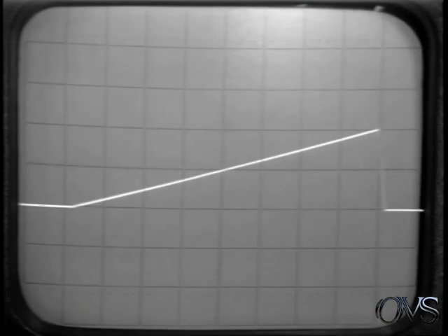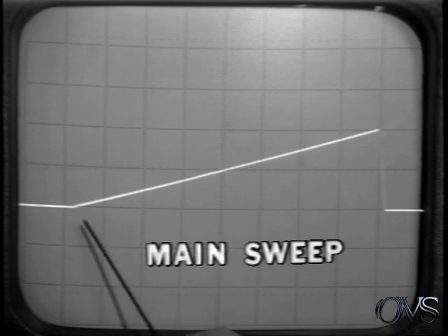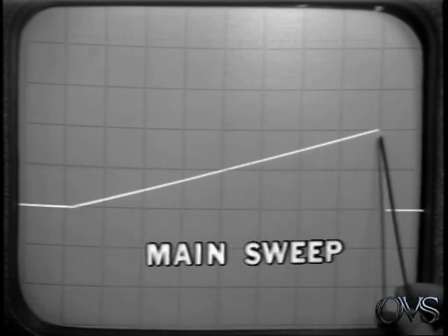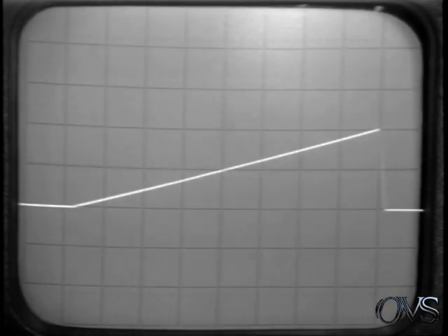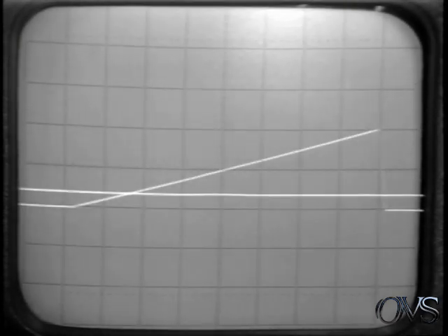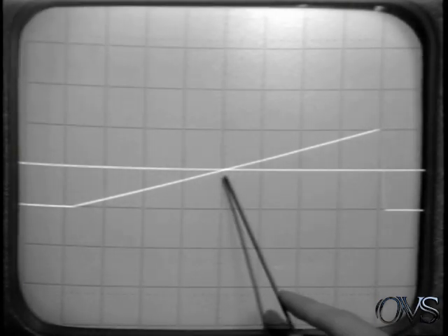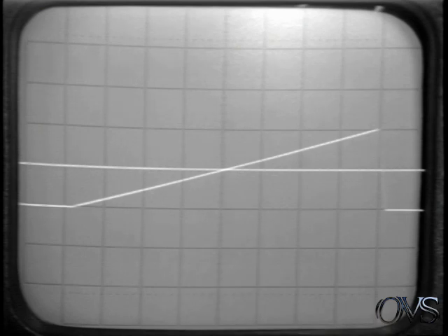On the monitor oscilloscope, the output of the sweep generator is being displayed. This is a linear ramp and causes the beam to move from the left to the right of the 180 CRT at a calibrated rate. To gain an adjustable delay period, we compare the main sweep to a variable DC level. The amplitude of this level is adjusted by the delay control on the front panel of the time base. At the point of coincidence, where the main sweep just equals the DC level, the delayed sweep is armed.